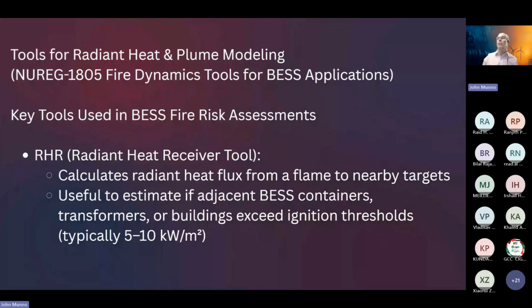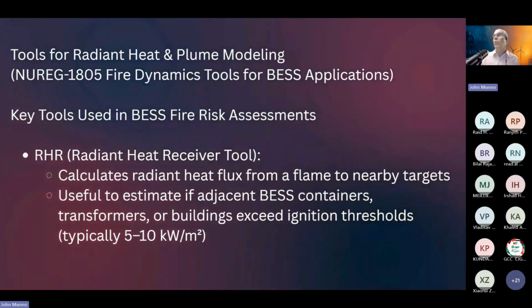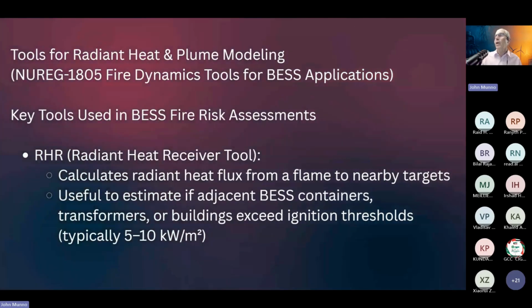Some of the key tools they have: the radiant heat tool, which will help you determine what the radiant flux is at your target. This is good for fire protection engineers if you've got generator step-up transformers as well. If you have a station service or auxiliary transformer and a generator step-up transformer, and there's a fire on the station service transformer, will there be enough heat to cause damage to the GSU if I don't have a firewall? This tool is very helpful in determining, especially for existing installations, will I need a firewall or not?